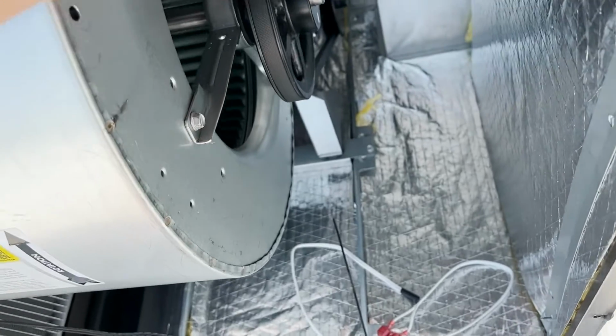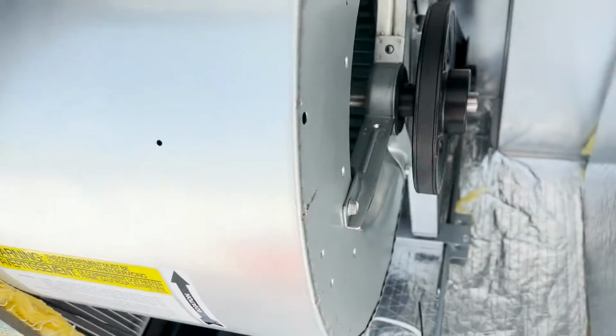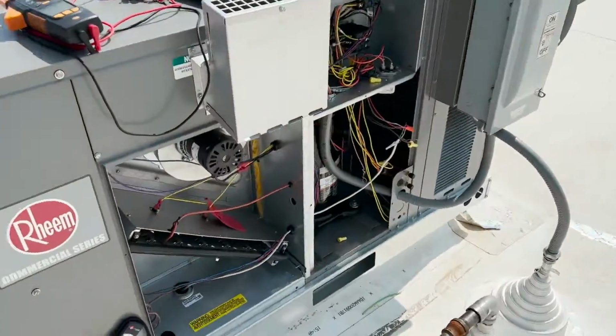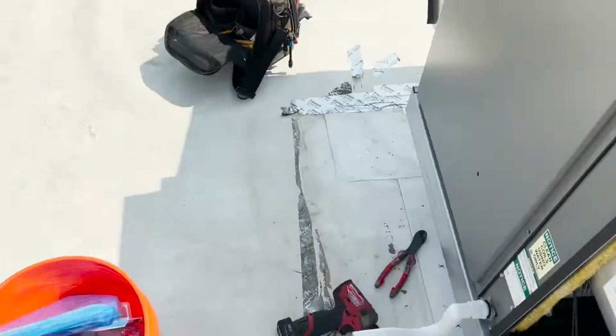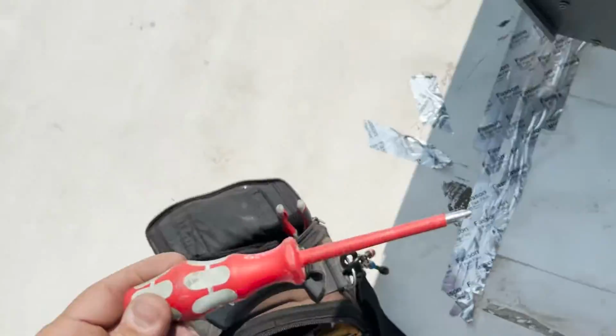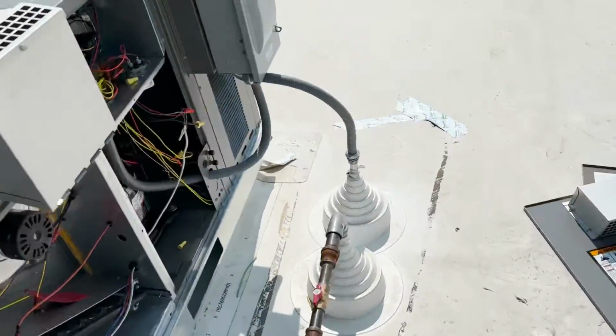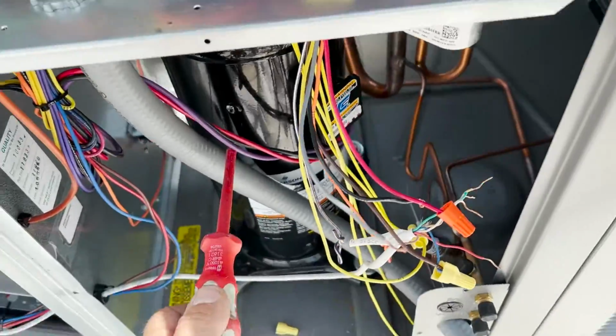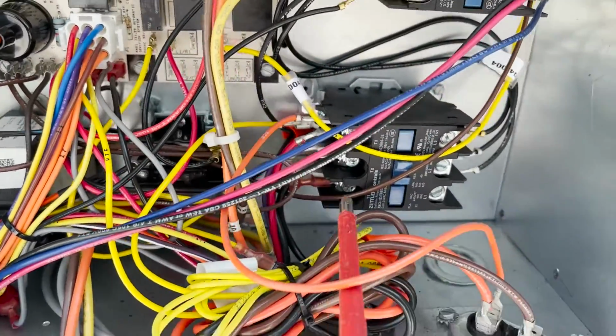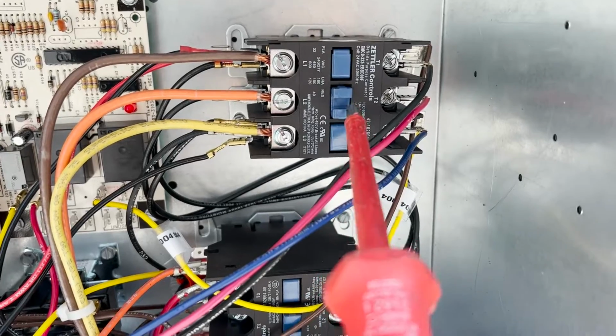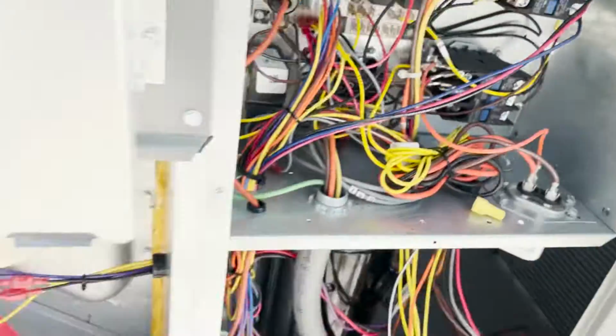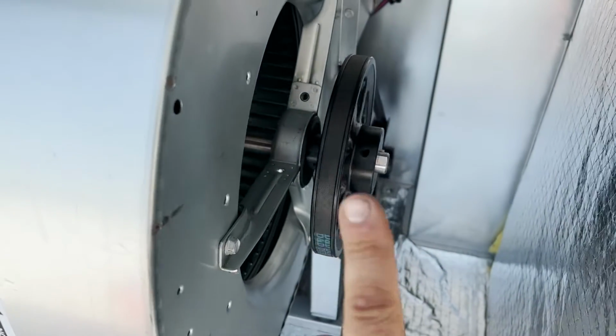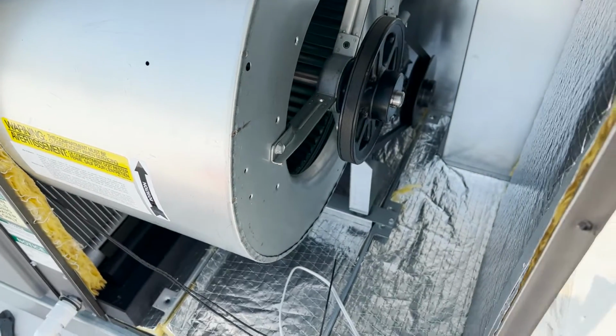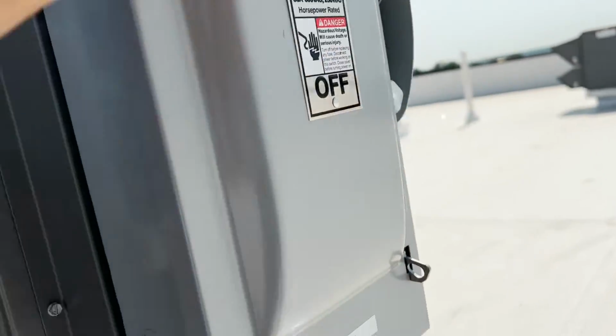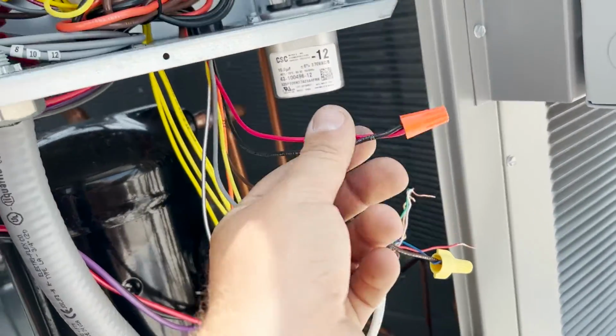All right, real fast, we're going to check rotation, right? So the manufacturer's real nice about giving us an arrow, right? So we want to see this rotate in that direction, right? So we're going to come over here with our tool that we had ready this whole time, like insulated. We're going to bump our blower contact. You can see, so these are purple, red, black, right? Purple, red, black, that's the compressor, so this is the blower, right? Let it run for a second, and jam over here. And see how it's spinning the correct direction. So now we're safe to run this blower. For our gas brush. So we are jumped out, right? Red to white.